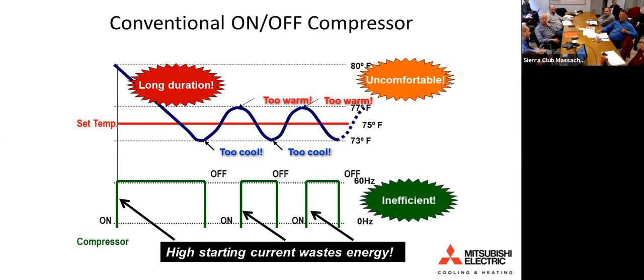It's not good for the compressor. It's not good for comfort, and certainly not good for energy efficiency. It has a very high starting current, and it wastes a lot of energy. And utilities also really don't like this slamming on of a system that comes on at full bore and then comes off and then comes on.